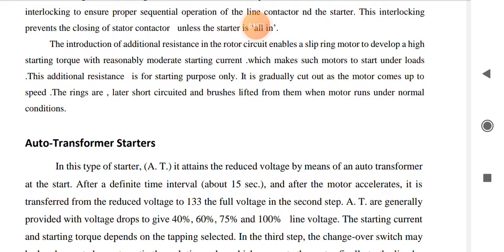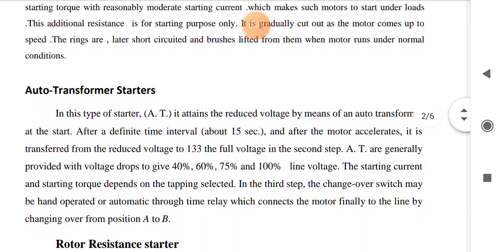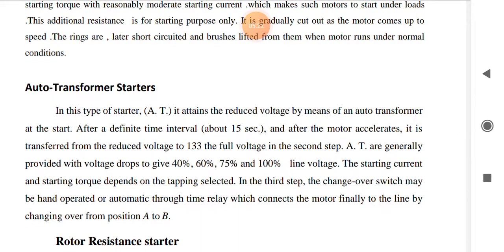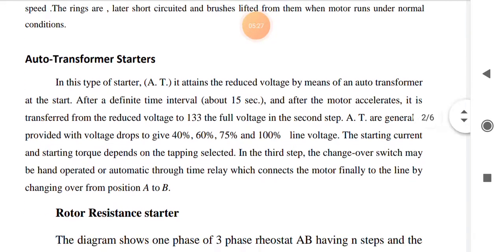The introduction of additional resistance in the rotor circuit enables a slip ring motor to develop high starting torque with reasonably moderate starting current, which makes such a motor able to start under load. The additional resistance is for starting purposes only. It is gradually cut out as the motor comes up to speed. The rings are later short circuited and brushes lifted from them when the motor runs under normal condition.